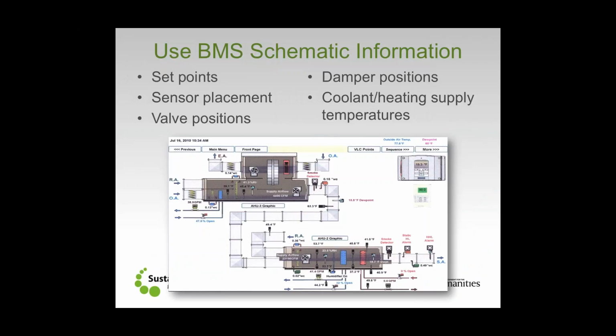Now the other part that plays into this, and the other part that we can spend some time on in terms of that documentation process, is looking at the building management system and understanding what the different points of control are and what we have available to us. Not just what the set points are for various components, how the cooling coil runs, or how the set point condition for the supply air, or how supply air gets decided upon. Is that determined by the condition in the space, or is it a set condition leaving the heating coil at all times? But also, where are the sensors that determine how the mechanical system actually runs? Are we working off of return air sensors or supply air sensors, or sensors out in the space, or maybe an average of multiple spaces throughout a zone?